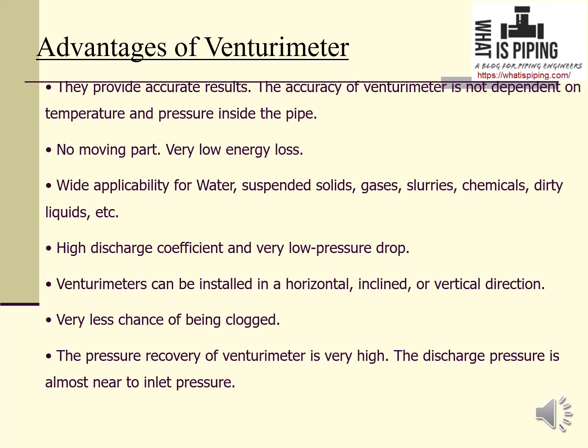The advantages of venturimeters include: accurate results that are not dependent on temperature and pressure inside the pipe; no moving parts; very low energy loss; wide applicability for water, suspended solids, gases, slurries, chemicals, and dirty liquids; high discharge coefficient; very low pressure drop; and flexibility — they can be installed in horizontal, inclined, or vertical directions.